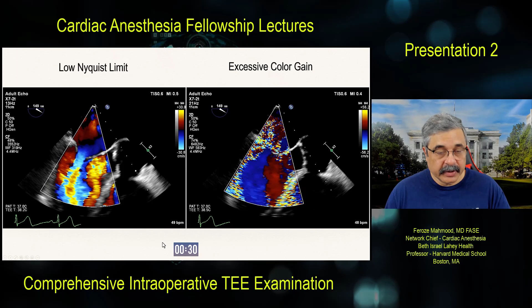The one on the right here has an excessive gain, which means the gain has been increased from 48% to about 74%. The upper velocity limit is 0.5 meters per second in either direction, but there's excessive gain. This is analogous to 2D gain when you increase the sensitivity and amplitude of all the returning signals. And the difference between a low Nyquist limit and excessive gain is that in excessive gain, what we are seeing is called bleed over, in which the color flow signal is beginning to overlay the grayscale signal. That's how you differentiate between low Nyquist limit and excessive gain. Despite the low Nyquist limit, the boundaries between flow and no flow and flow and tissue are very easily appreciated, whereas the ones over here cannot be seen as well. So that's one of the changes in the controls that you can look at.